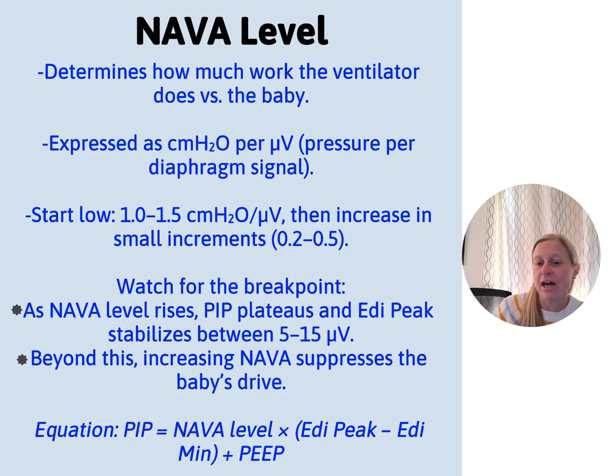PIP is not a set value on NAVA, right? So that's why we have this equation here. If you want to know what your PIP is, you need to know what your NAVA level is. You need to get those Edi peaks and mins that we just talked about, and then we're going to get our PEEP in. So I want you to remember this. We need to do our NAVA level times the Edi peak minus the Edi min plus the PEEP.